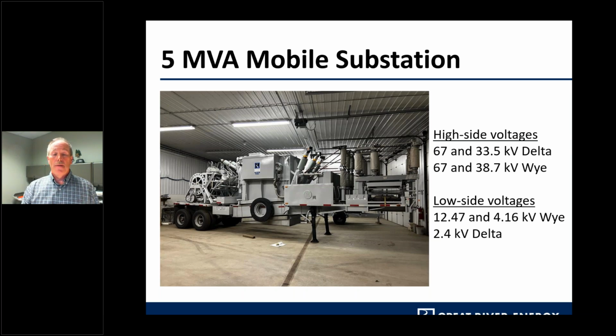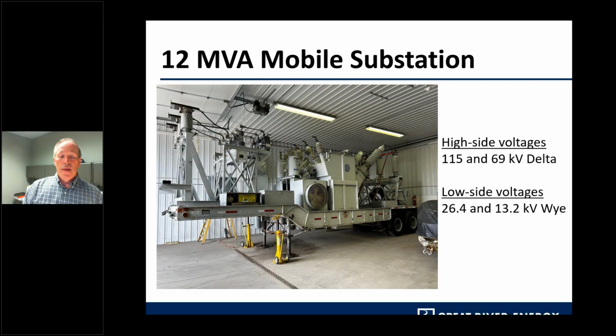Here is our 12 MVA mobile sub, also located in Buffalo, Minnesota. This one is configured a little differently from our 5 MVA mobile sub, and there's a separate high side switch trailer needed because of the 115 kV voltage — it just couldn't be mounted on the existing trailer. Going again from the right to the left, you have your high side H bushings on the right, and then toward the left you have your low side X bushings, then through the metering instrument transformers, then to the recloser, and finally to the cable terminations. This mobile also needs a separate trailer for the cables, whereas the other 5 MVA mobile had that as part of it. This one has a separate cable trailer that needs to be installed.